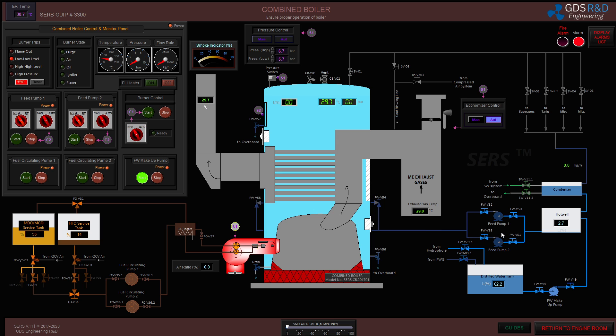I will be using both feed pumps. I will open the ventilation valve before starting the feed pumps — I don't want to build up air pressure inside the boiler. I will start the feed pumps in auto mode. This will take a little while to fill up the boiler with water, so I will switch to other operations in the meantime.